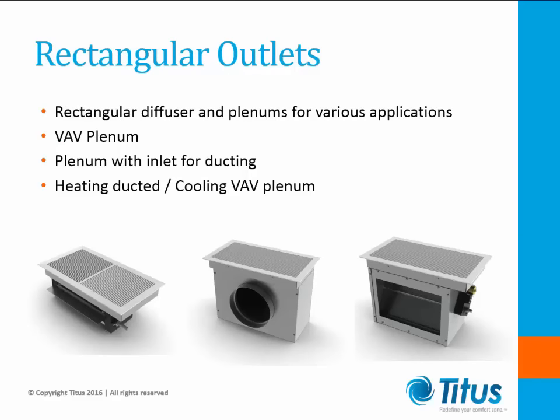There are also a variety of rectangular UFAD diffusers available. Some include plenums for ducted connections beneath the floor, others include manually adjusted dampers for balancing or actuated dampers to provide VAV control. Some are designed to allow the diffuser to receive air from multiple sources — for instance, a plenum with an actuated damper could be ducted to an underfloor terminal unit for heating or receive cool air directly from the floor plenum. Some of these devices have lay-in grills that can be turned in various directions to create different air patterns on the floor or to direct air vertically for perimeter applications.